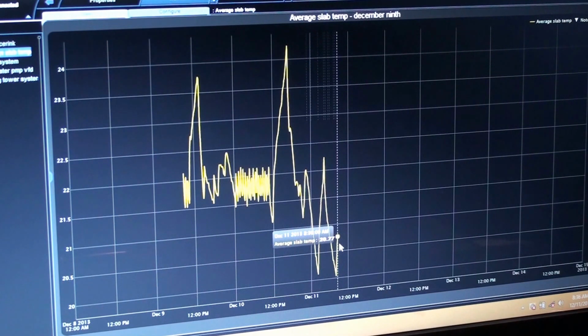Now, the differential setting on this, I have at the moment through the night 2 degrees differential, which brings it down past the set point by 2 degrees. To narrow that in, you just close in on the differential. You can lower the differential to 0.25 degrees, 0.50 degrees. So it'll be either 1/4 degree differential or 1/2 degree differential to be able to control the ice temperature with a tighter bandwidth to maintain the temperature of the chiller.